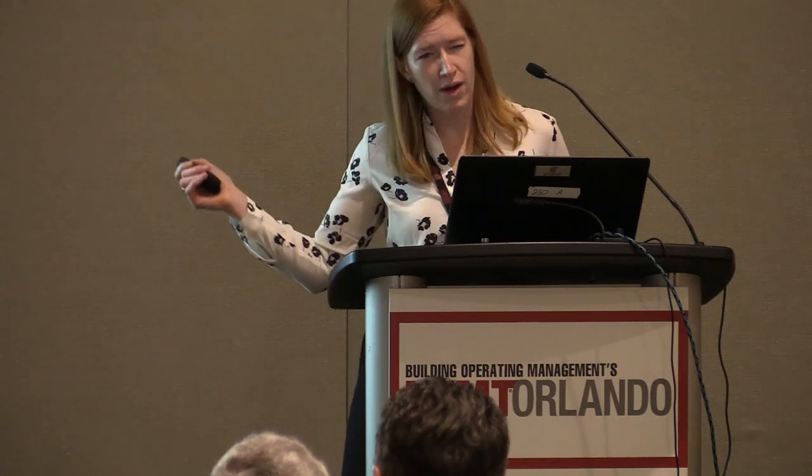So this is an example of a comfort report that focuses on these very things. So this is a comfort KPI. It's the percent of time that zones are meeting their temperature set point throughout the entire building. So this facility is at 89%. Down here is the best opportunities to improve comfort. Trying to give it a positive spin and saying these are your worst terminal units. So these are the 5 terminal units that have the worst comfort. They're not meeting their set point most of the time.